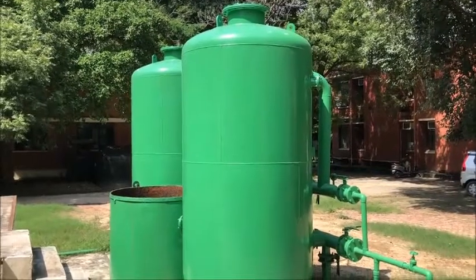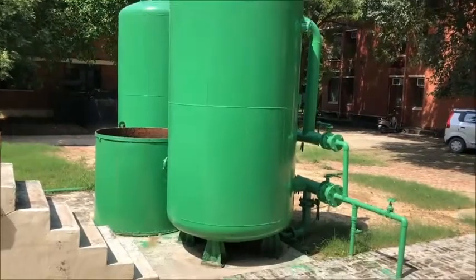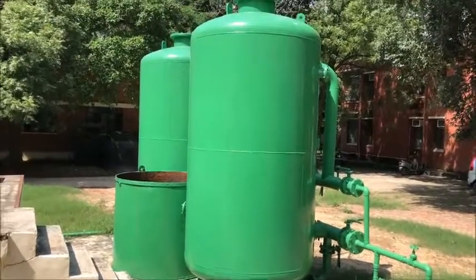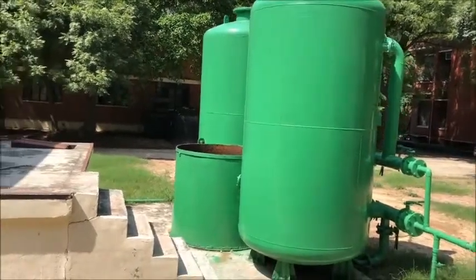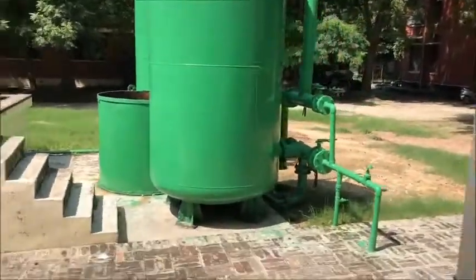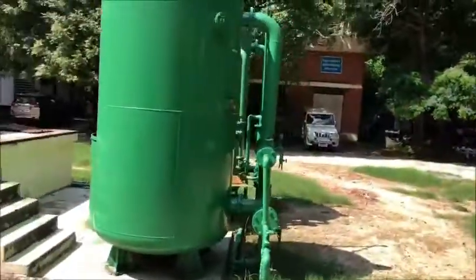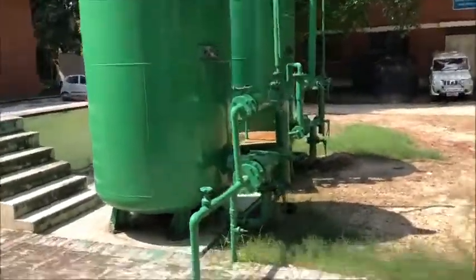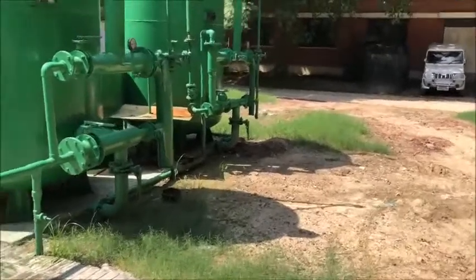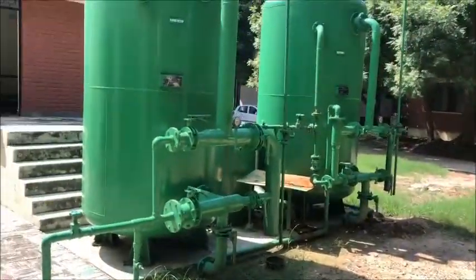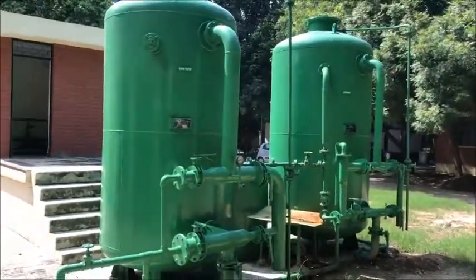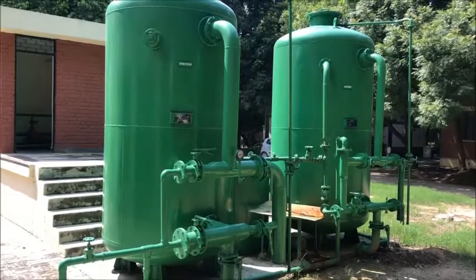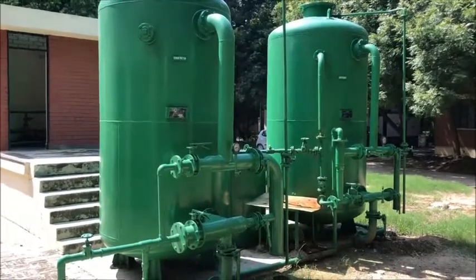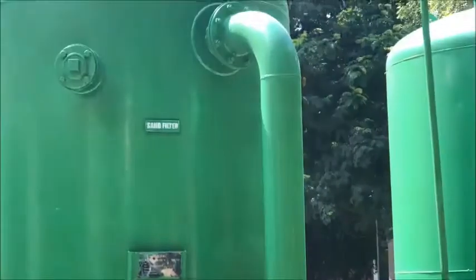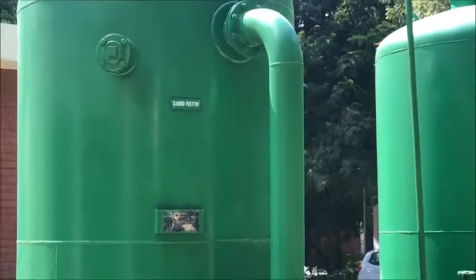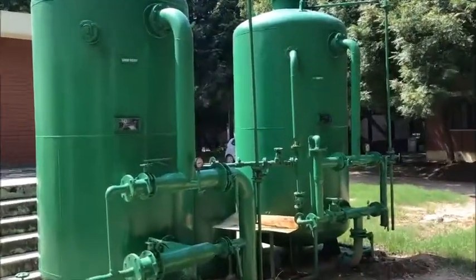Before going to the cooling tower, I just want to tell that we require soft water which has to be circulated in the condenser water piping system through the cooling tower. Soft water is required because there is a big challenge of scale formation inside the condenser water pumps and inside the condenser shell. So it is of utmost importance that we should use soft water.